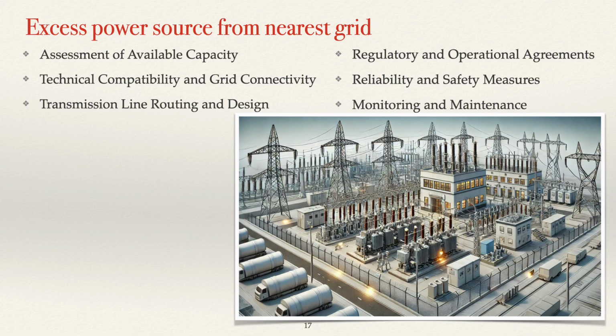Engineers conduct load flow analyses to determine if the nearest grid substation has sufficient excess capacity to meet the new demand without affecting existing consumers. This study evaluates the load profiles, existing transmission lines, and substation capabilities, ensuring that there is an adequate reserve margin. A buffer of excess generation capacity on the grid is essential for handling unexpected spikes or additional loads.